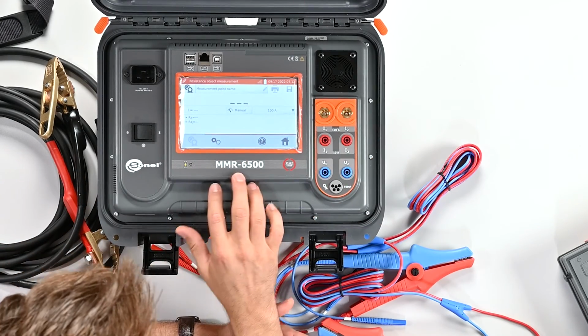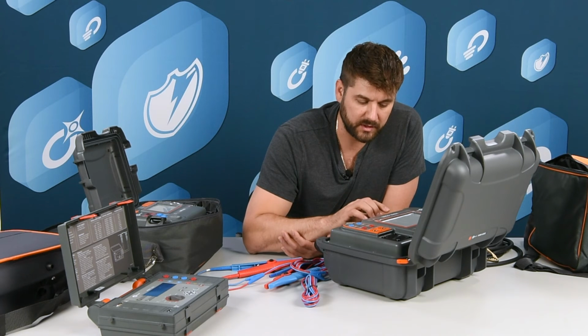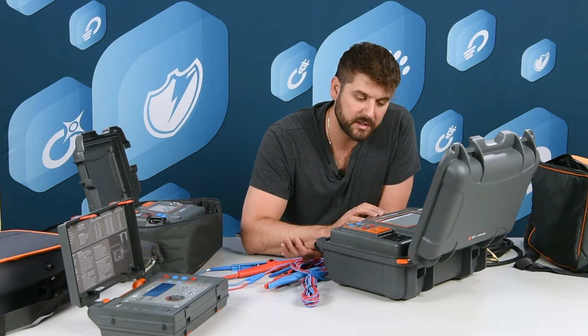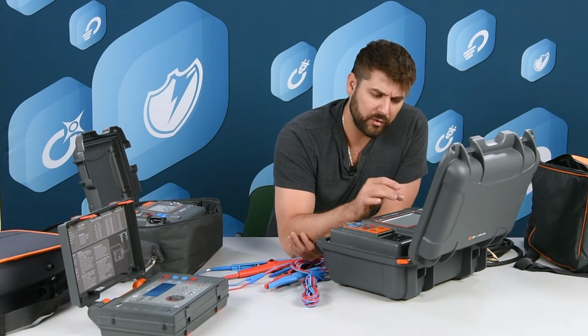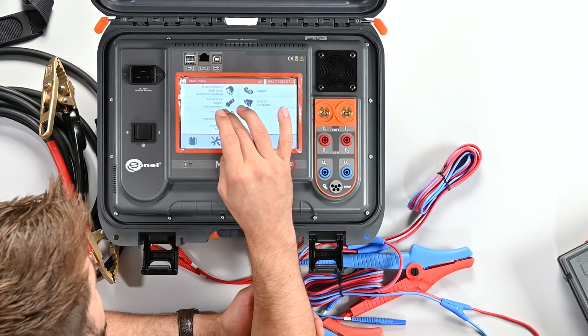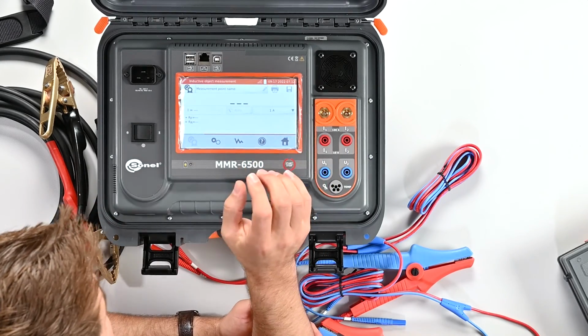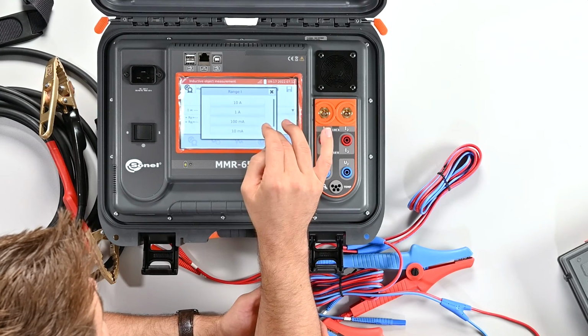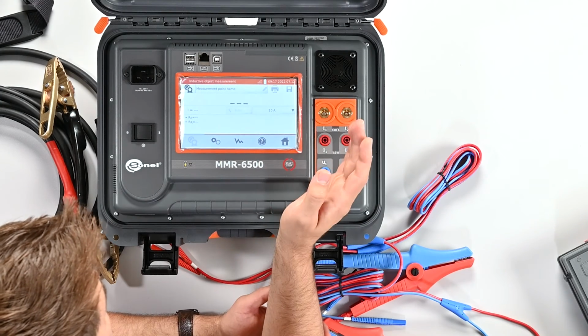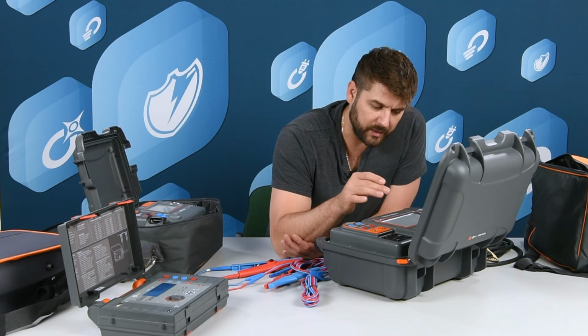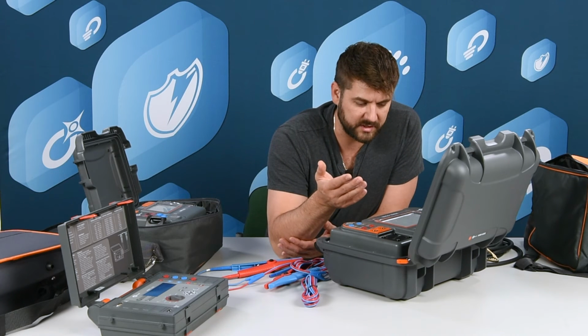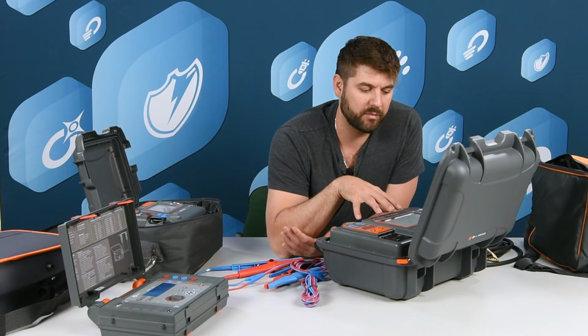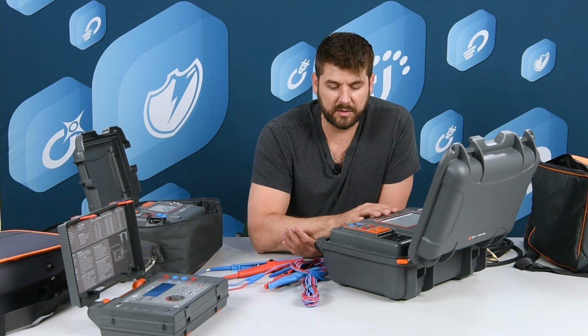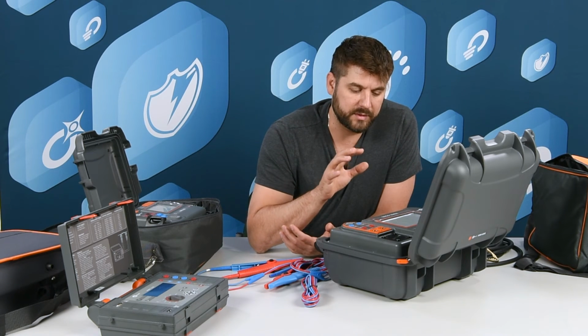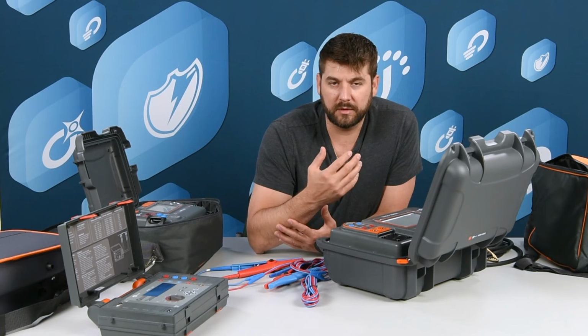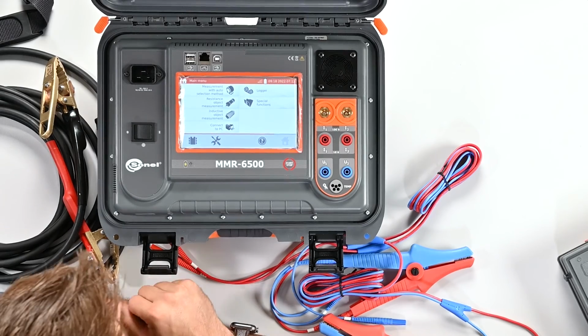This device here, this is our MMR 6500, it'll do 100 amps. MMR 6700 will do 200 amps. However, if we're in the mode where we're doing an inductive object, it's going to limit to 10 amps. An inductive object is normally tested by a winding resistance meter, but we have built the capability into these MMRs. Although it still takes some time, we will get an accurate measurement.